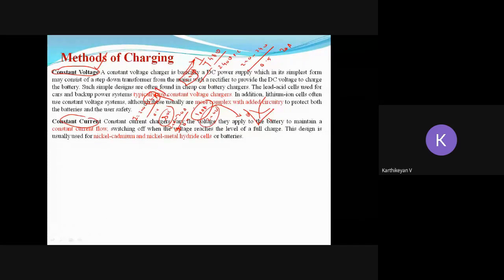Based on the SOC, your voltage starts to rise. So when voltage rises from 200 to 240, 260 like that, current starts decreasing from 100 ampere, 80, 90, 70, 60, 50, 40, 30, 20, then 5, then 2, then 0. So this much change in current happens as you charge. I don't want that. Constant voltage means your current will vary, and I don't want that. I have to make it constant current.